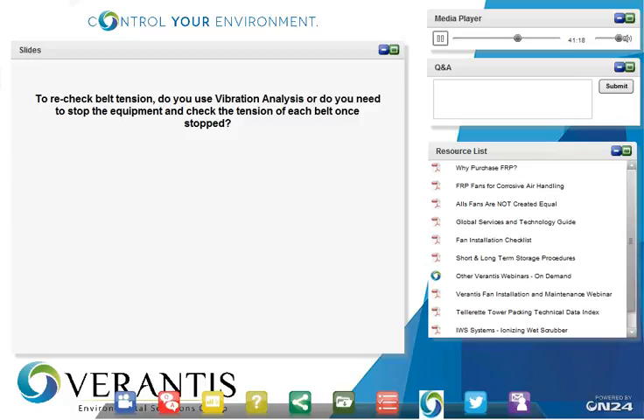To recheck belt tension, do you use vibration analysis, or do you need to stop the equipment and check the tension of each belt once stopped? Typically, to check belt tension, you would need to shut the fan down. Vibration levels can come from many things other than just belt tension. You could have buildup on the fan. You could have looseness in a fan bearing. So in order to do it properly, you would need to shut the fan down to verify belt tension.